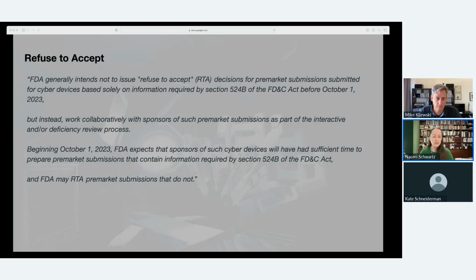So do we anticipate FDA adjusting or putting out additional guidance on how to better make the submissions to avoid RTA? There is the original pre-market guidance from 2014. The content in there has been expanded upon largely, and there's a lot more detail in the draft guidance from 2022. But right now, if you are trying to prepare your submission to avoid RTA in October, look at the way that the Act was amended, look at the 2014 guidance and make sure you have everything that's in there, and look at that draft guidance and forecast ahead what FDA is likely to be asking for.